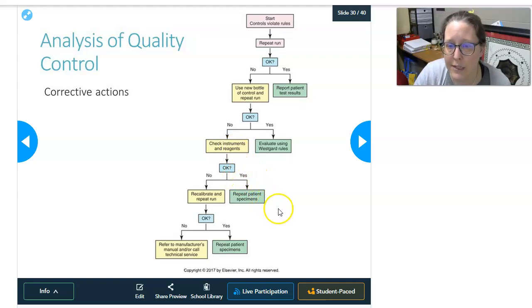And if that fixes it, you can repeat your patient specimens of what you've been running, make sure everything's good, and your quality control is in, all of that, right? You can report out your patients. If swapping to new reagents or doing some maintenance and stuff like that didn't fix it, your QC is still out, then because you reran your QC after you did your maintenance or changed your reagent, you are going to recalibrate and run your QC again.